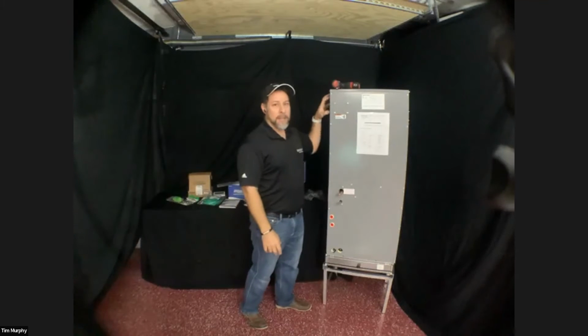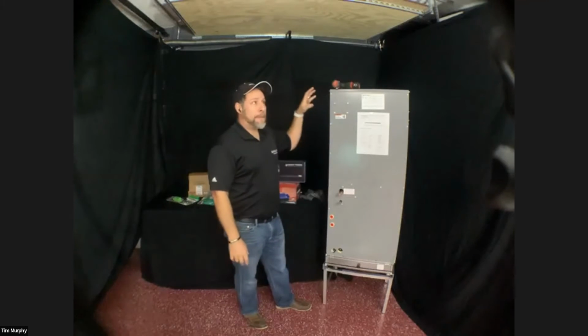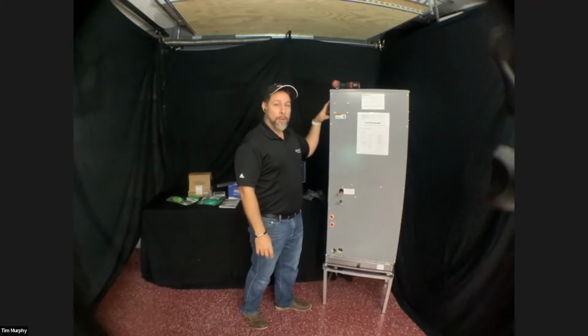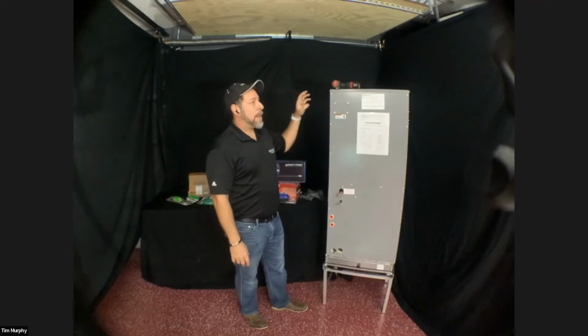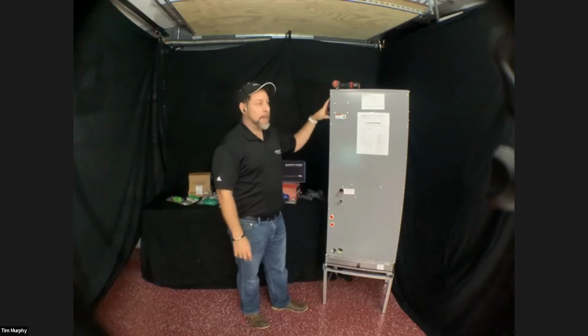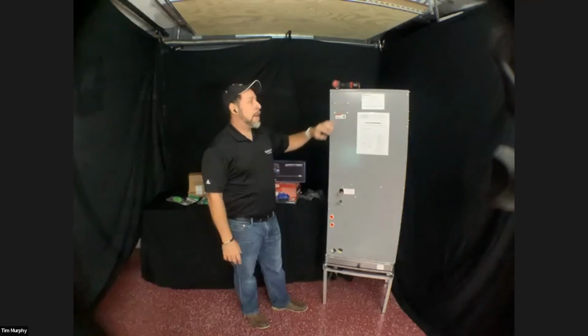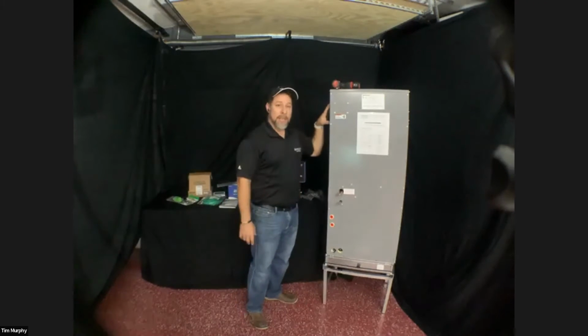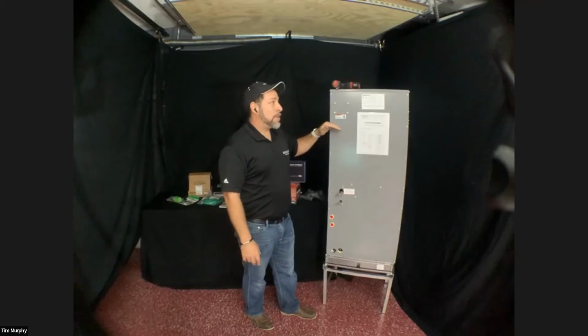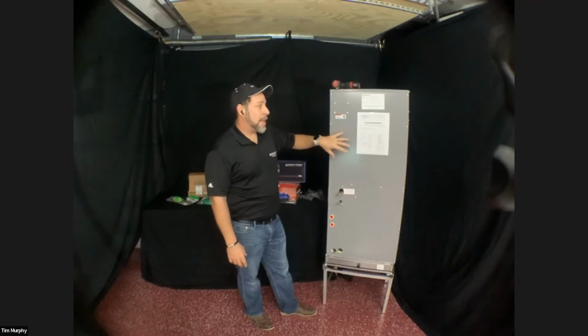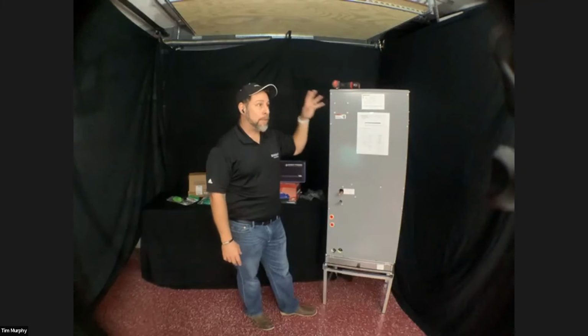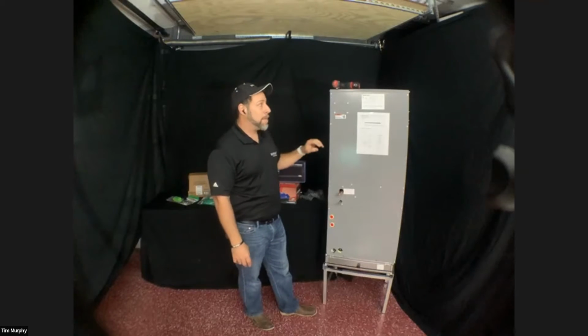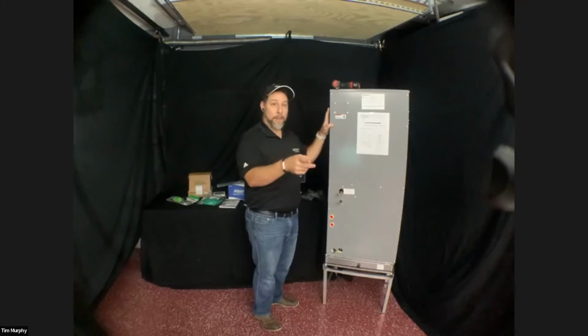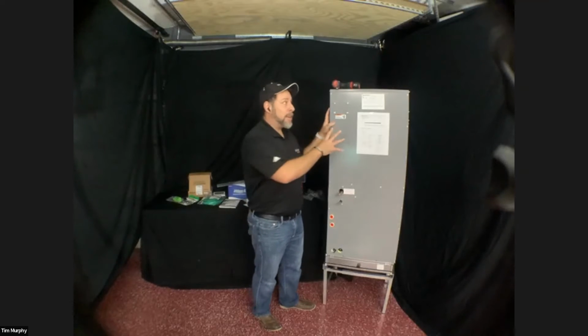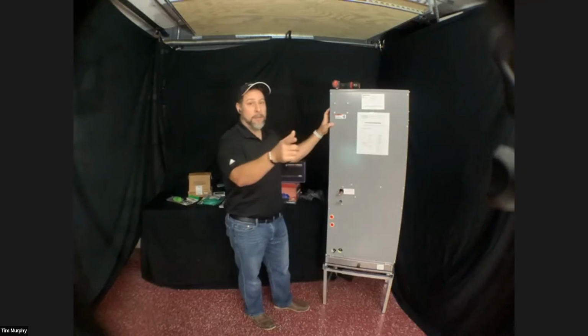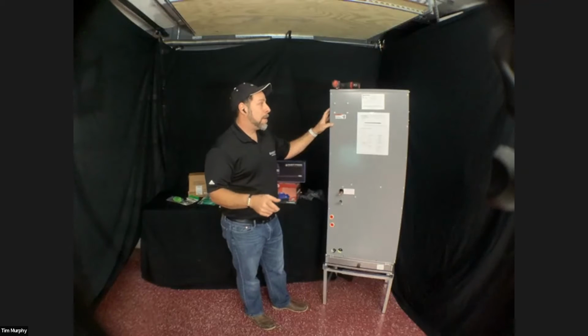So you're not going to need the additional heat strip kit. If you've got an inspector who requires it, or you do need it, then by all means we can order it, and that's something that can be installed. I'll show you where that's going to go later. But since you don't need to install a heat kit, you're not going to need a lot of voltage. There's just a constant torque motor in here. It's not going to pull more, I'd be surprised, than 2 amps. So running that 14/3 power wire is all you're going to need to power up the system, and then the 16/2 stranded shielded wire as well.